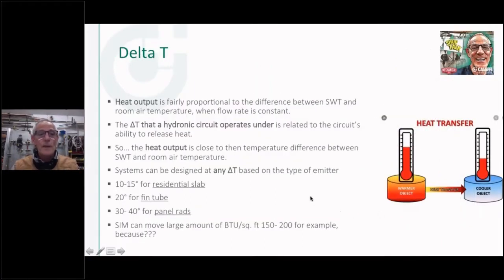So what we know also is that the heat output is fairly proportional to the difference between the supply water temperature, the temperature of the wall or the heat emitter, whatever it might be, and the room air temperature. It's a pretty linear thing, and that's why when we use an outdoor reset control on a boiler, the two follow themselves pretty closely. We step up or down the temperature going to the house as the temperature outside or inside the building changes. So it's a pretty linear relationship to move heat based on the temperature difference.